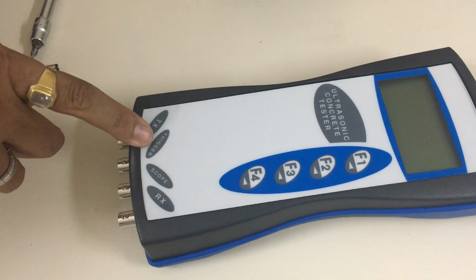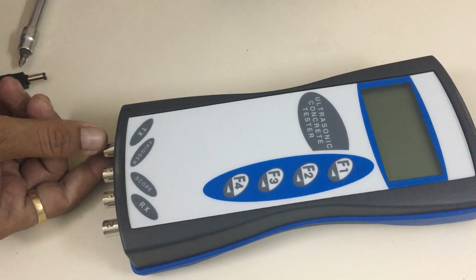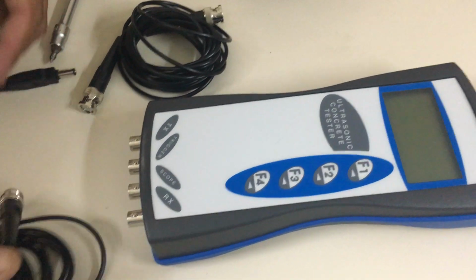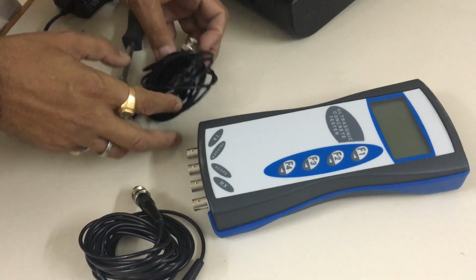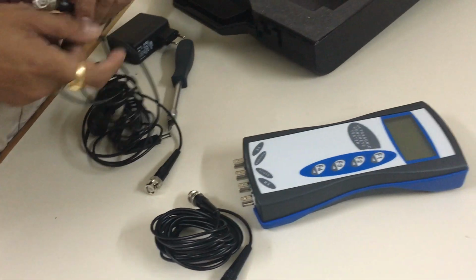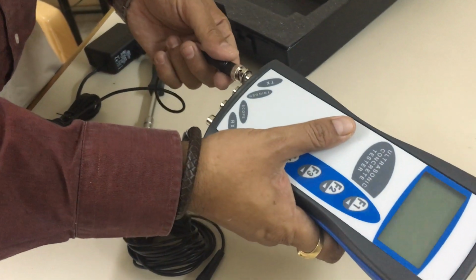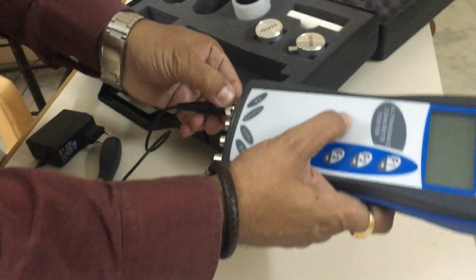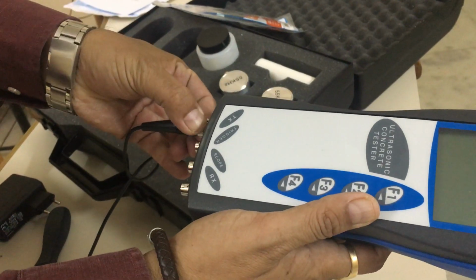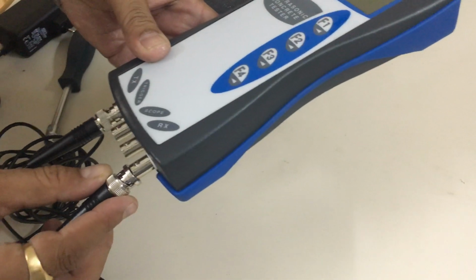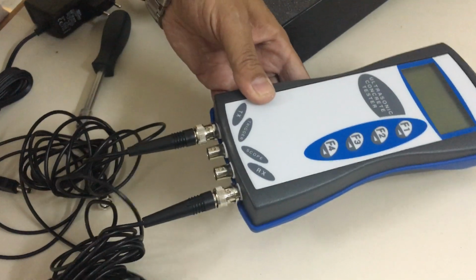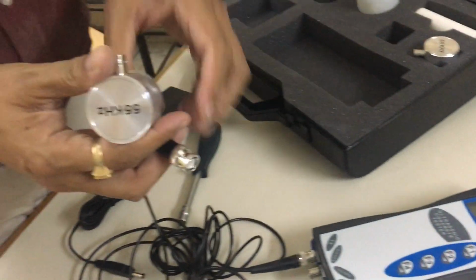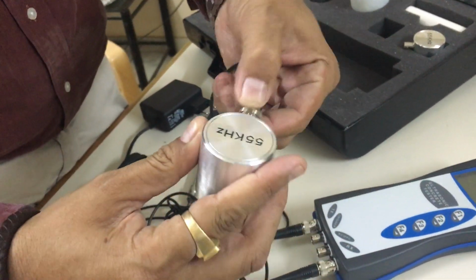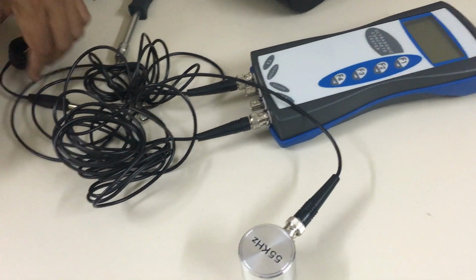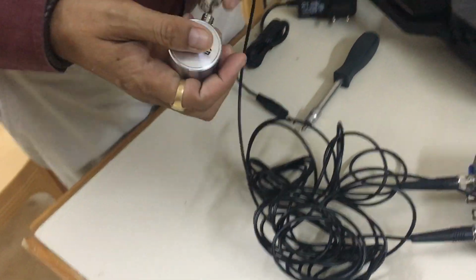TX, RX, trigger and scope. Connect these two cables at TX and RX respectively. You can connect them anywhere because both the cables are the same. So I'm just connecting this cable to TX. You can see I've just put it in and twisted it a little bit. Similarly here to the RX. The other end is connected to the ultrasonic probe the same way. 55 kilohertz probe. Both are 55 kilohertz probes.